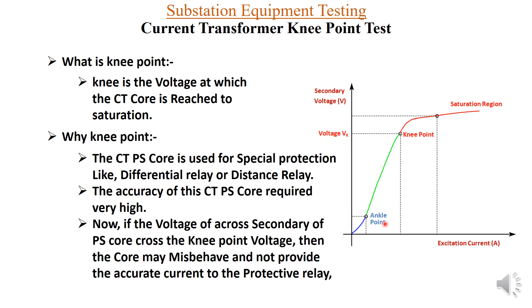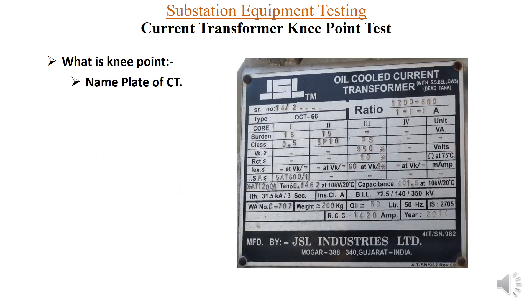We also have an ankle point on this graph. The ankle point is used for the metering core, while the knee point is very important for the PS core, which is the special protection core.